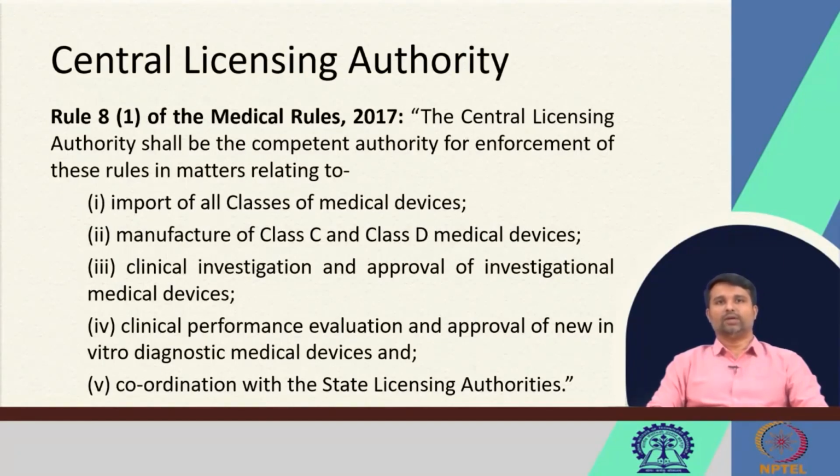The central licensing authority shall be the competent authority for enforcement of the medical device rules in relation to import of all classes of medical devices, manufacture of class C and class D medical devices, clinical investigation and approval of investigational medical devices, clinical performance evaluation and approval of new in vitro diagnostic medical devices, and coordination with state licensing authorities. So, devices or activities which require stringent control come under the regulatory purview of the central licensing authority.